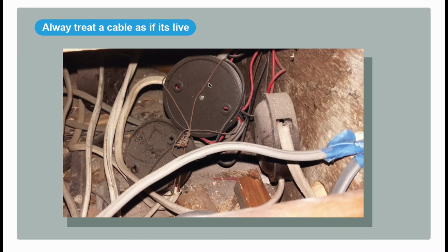You haven't got a junction box, so you can't get a live and neutral test or a live earth test, you've just got the cable coming through. You can use a volt stick and see if there's any voltage in it, but that's not a reliable method of proving dead. You just have to be very, very careful. I always try and trace out cables so I know what's what. When you're removing cables, you want to find both ends of it, and you know that you're not interfering with somebody else's electrics. So you've got to take good care when you're stripping out. Don't just think the power's off and start ripping everything out, because you might be ripping out downstairs' electrics as well. They won't be very happy, and it's also potentially dangerous.